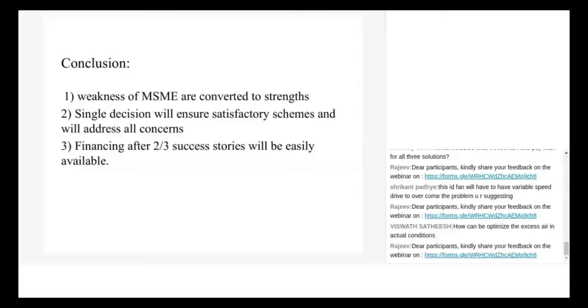How can we optimize the excess air in the actual condition? No, never do that with solid fuels, because with solid fuels, if fuel is coming continuously, then you can optimize air. But here, fuel is fired in lots. He will see the pressure, then take out ash, then fire the new fuel. So about every half an hour there will be a firing, and he has to open the door and take out the ash, because there are two or three things he has to do in solid fuel fired boilers. It's not only fuel to air management.